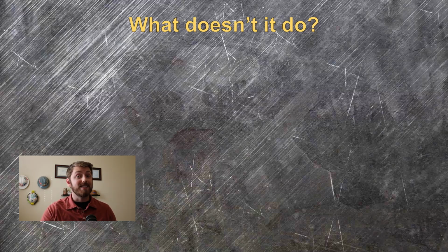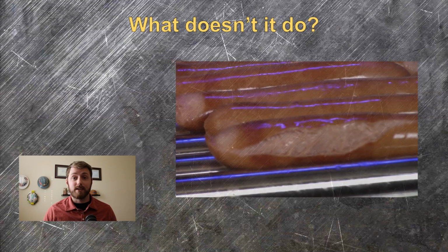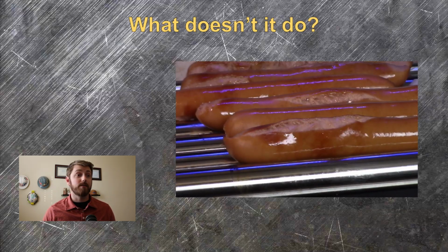Number two, it definitely doesn't make energized work safe. It does nothing for the shock risk. The system is still hot and any energized conductors will shock you and they will kill you. The breaker will take longer to trip than it takes your heart to become irreparably and fatally damaged. It's likely that the impedance of your greasy body is high enough that the breaker won't trip anyway, so you'll sit there and sizzle like a neglected hot dog on the roller at 7-Eleven.